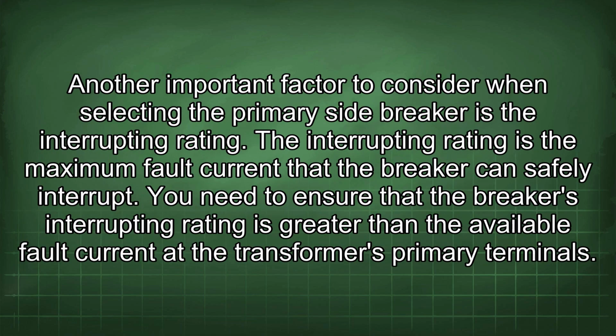Another important factor to consider when selecting the primary side breaker is the interrupting rating. The interrupting rating is the maximum fault current that the breaker can safely interrupt. You need to ensure that the breaker's interrupting rating is greater than the available fault current at the transformer's primary terminals.